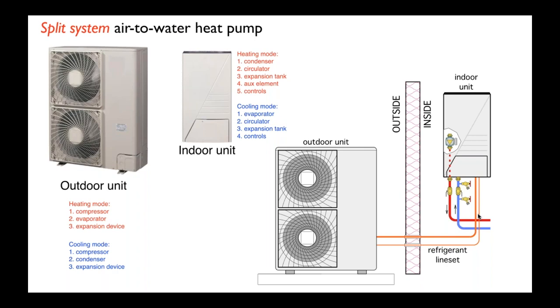So if it's a company that only does water side work, that doesn't have refrigerant training, a split system will probably require some type of a subcontractor or a person that can attach that line set and evacuate it and then release a charge. Now, one of the technologies that has really pushed air source heat pumps along into what are referred to as either low ambient air source heat pumps, or sometimes you'll hear the term cold climate air source heat pumps, is a technique called enhanced vapor injection.